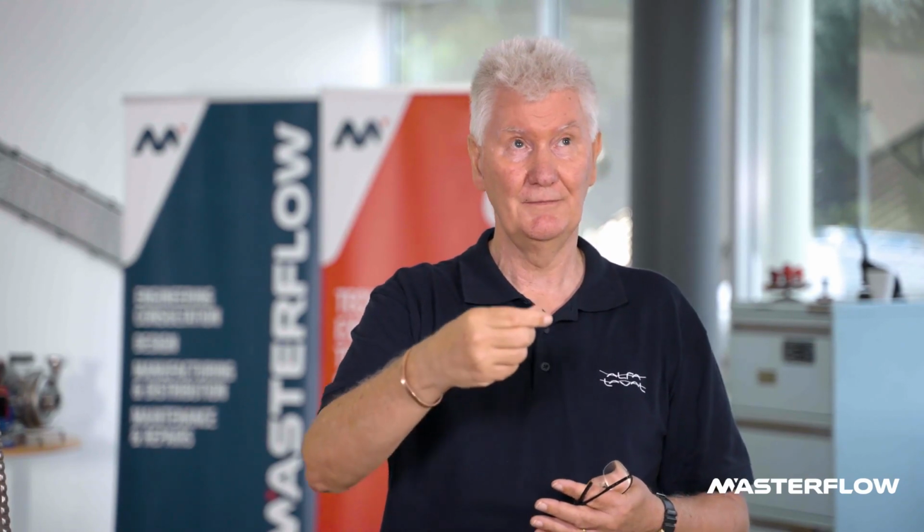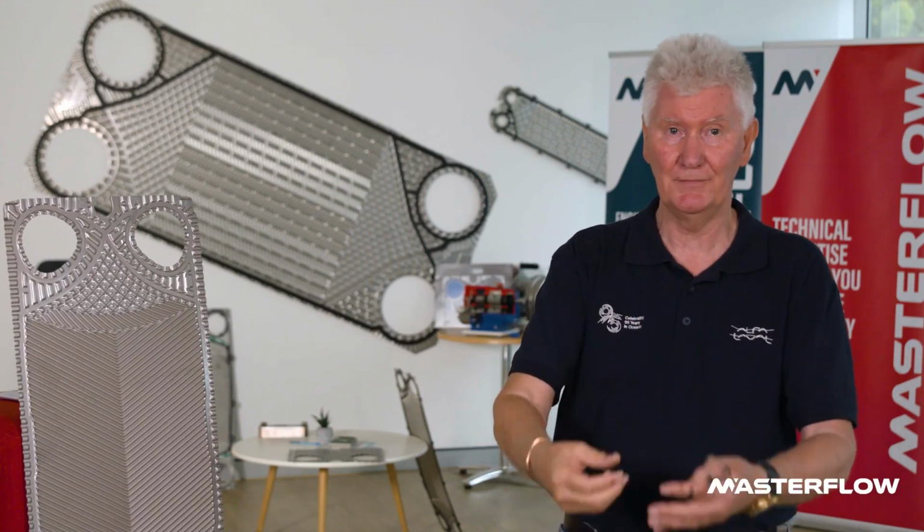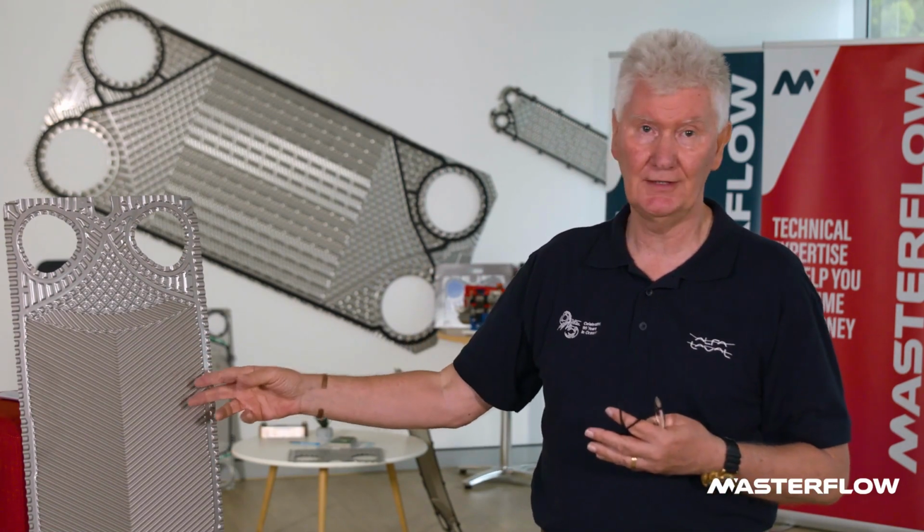But the larger the gap, the plate itself is less efficient. So you control excess area because you've got a less efficient plate, but you can control pressure drop. The design engineer has to manipulate this, and having 3 channel gaps allows us more options on the design.